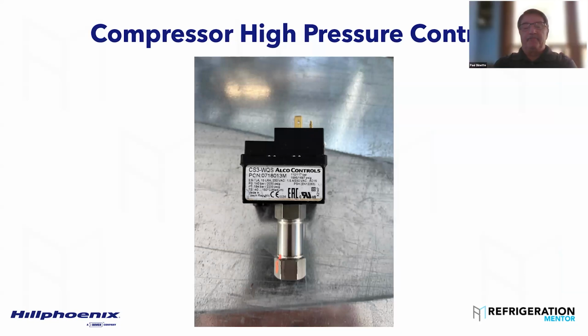One thing about the pressure switches, guys, be aware there's 2 different types of pressure switches. You have one for your 120 bar systems, which is 108, and then you have one for your 130 bar system, which is a 117. So be aware, don't just blindly order a pressure switch. Usually use the serial number for one of our racks when you order your parts so that they get you the right parts.